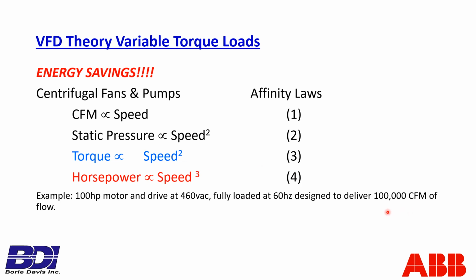So 50,000 CFM of flow, 30 hertz, 25% torque required, or static required. And finally, horsepower is relative to speed cubed. Again, if I need everything, I operate at 60 hertz, deliver 100,000 CFM, and 100% cubed is 1 times 1 times 1. 100% power is needed and available.